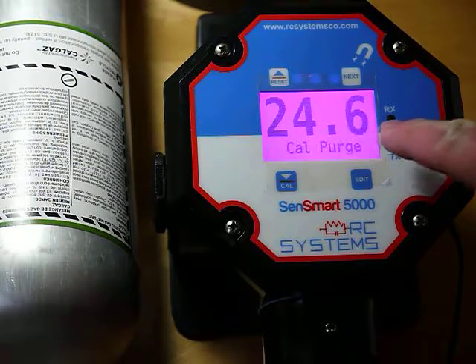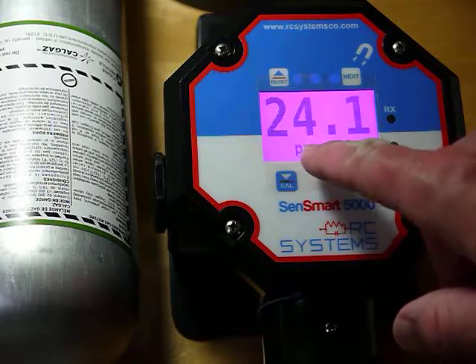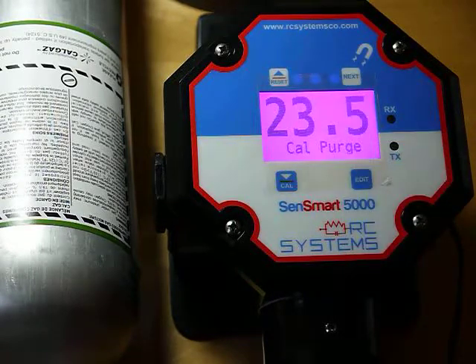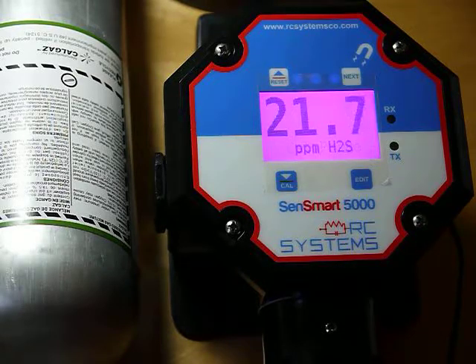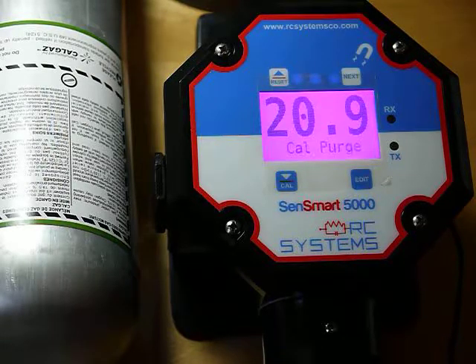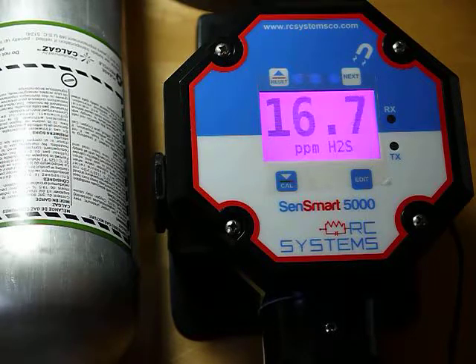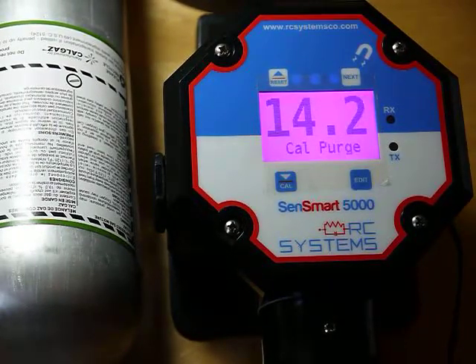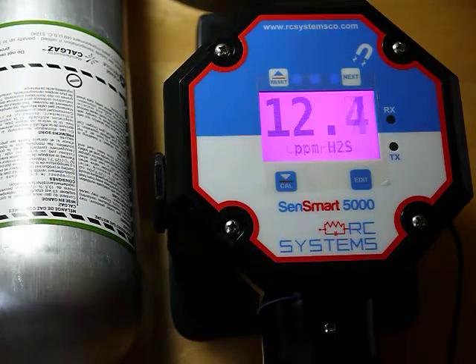Now because we've had gas on, this is actually showing calibration purge, which is nice. There is a way in this also to inhibit the alarms if you knew you were going to be calibrating. It's one of the first menus you get into, so that it wouldn't trigger. You could set the milliamp output during the calibration. You can also tell it to ignore the calibration and not trigger alarms. So this is rolling down. It's going to take a while to roll back down. This was a calibration.